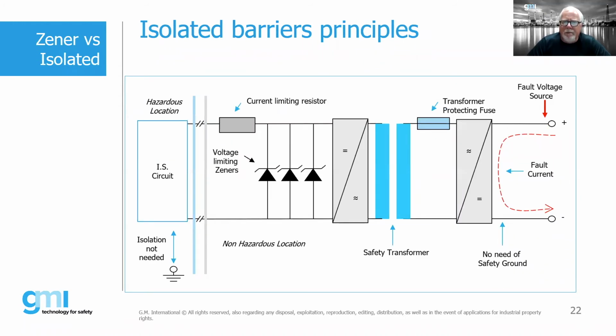Now we look at a galvanically isolated barrier and what is different. Again, we have our fuse and a current limiting resistor. We also have voltage limiting Zener diodes, but we've also introduced a safety transformer. If a fault condition is generated in the safe area and travels down this loop, it will hit this transformer and basically stay in the safe area. The safety transformer takes a signal, replicates it, and sends it on down the line. Notice that there is no requirement for a safety ground the moment we use isolated barriers. Galvanically isolated barriers allow you to use barriers without a dedicated earth. That's probably the major advantage of a galvanically isolated product versus a Zener barrier product.